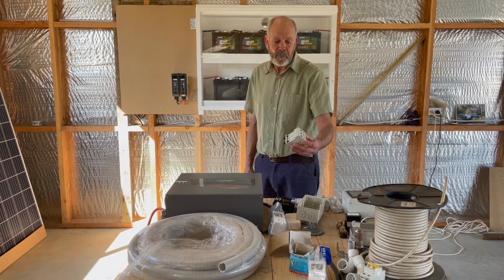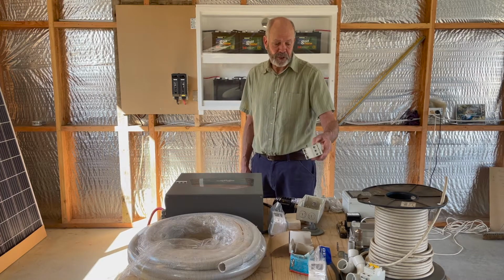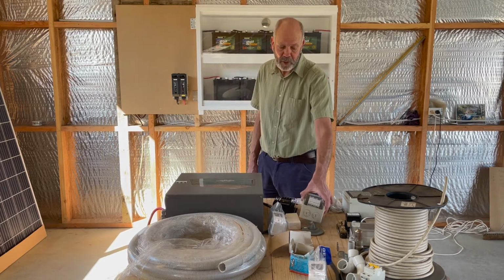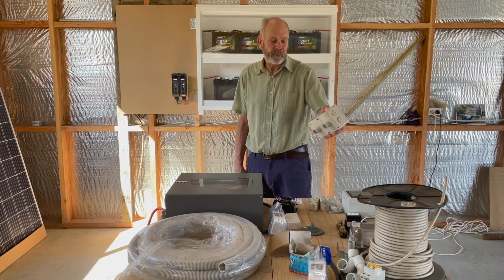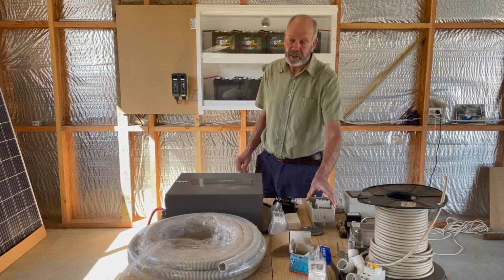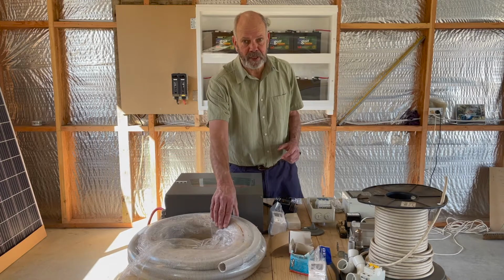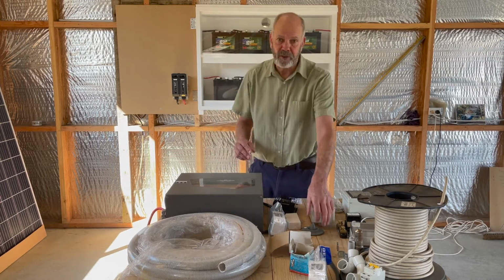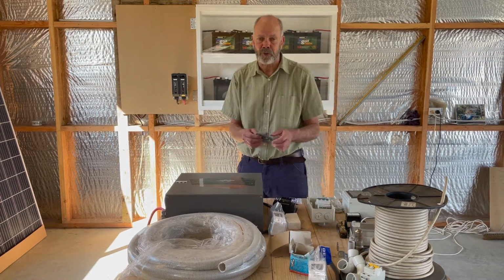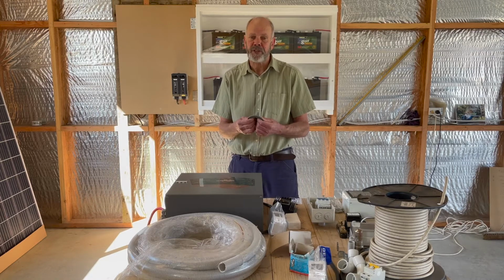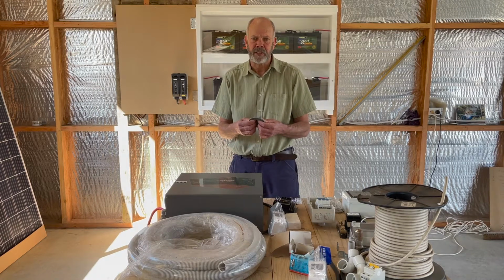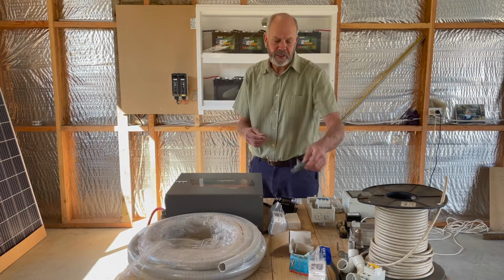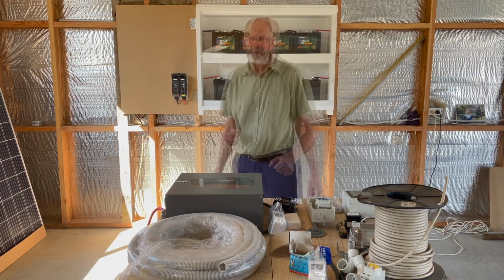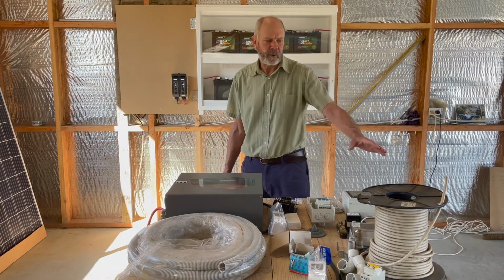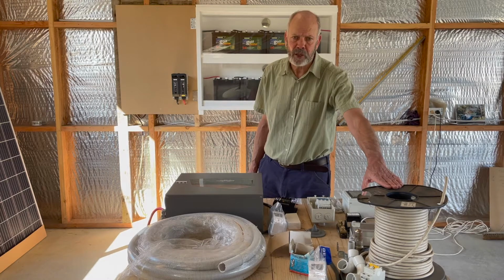Once I get the solar panels connected into this circuit breaker, I'm going to come out the bottom of the module box holding it. I'm going to come out the bottom of that in 25mm conduit. And I'm going to take that 25mm conduit down through the roof through a thing called a Dektite, which will seal the roof penetration and stop it leaking water. Then I'm going to come back down and I'm going to run 16mm builder's wire. It's a double insulated wire, very good for solar arrays.